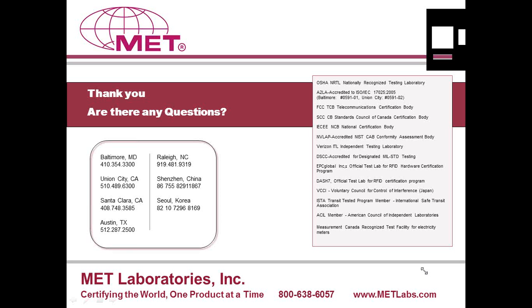Do the series tests in C12.1 have to start with test 15, then continue to test 16, and so forth, or could you continue with the same 3 units in the series test in any order? The interpretation there is no. Basically, you have to go sequentially through those tests in order. So we start at 15, run to 16, and so forth, and we end with tests 30 and 31 with that same set of meters. And again, those meters need to be compliant all the way through.